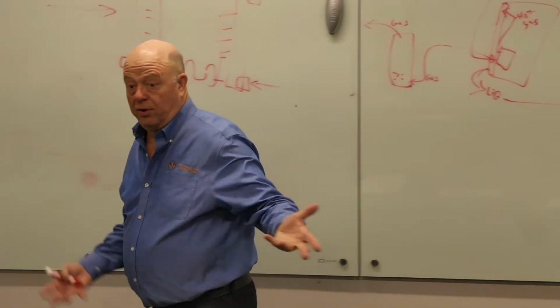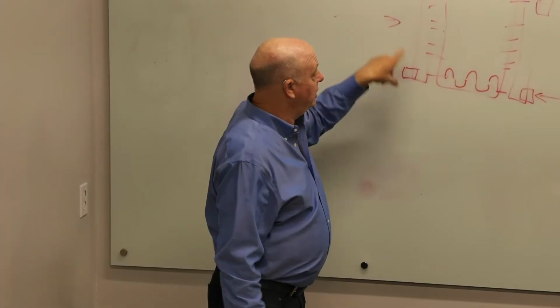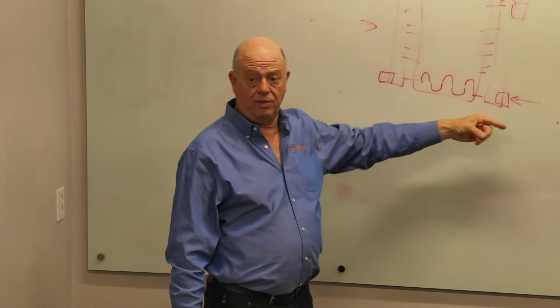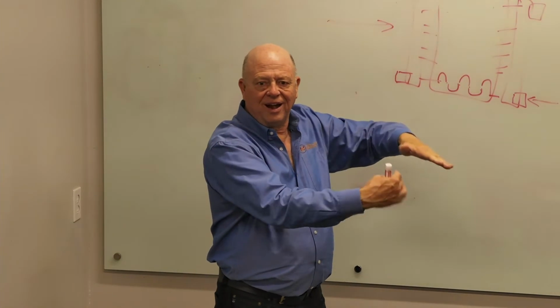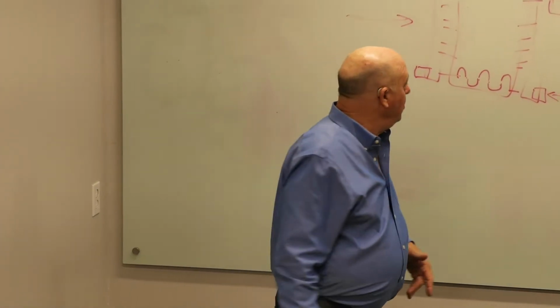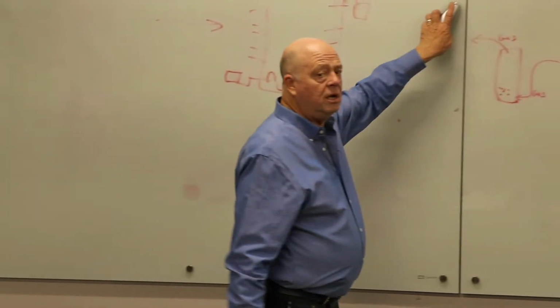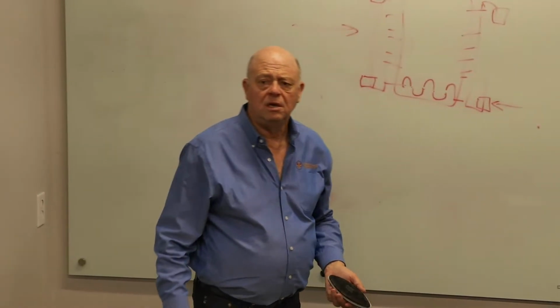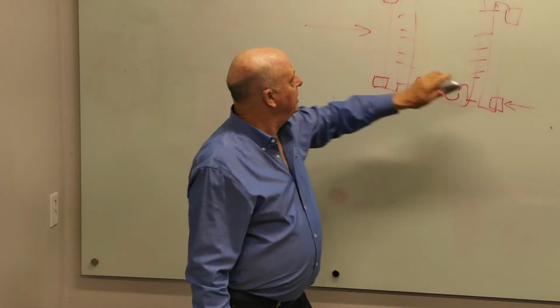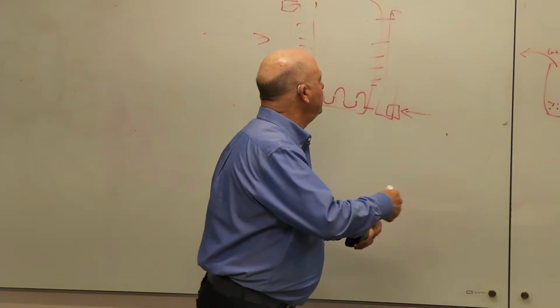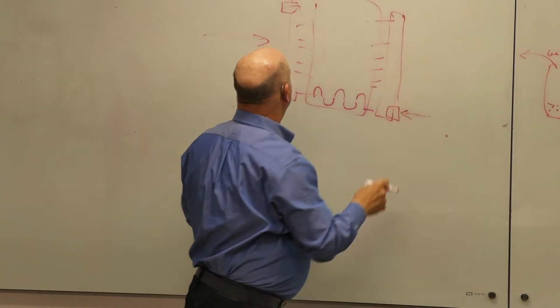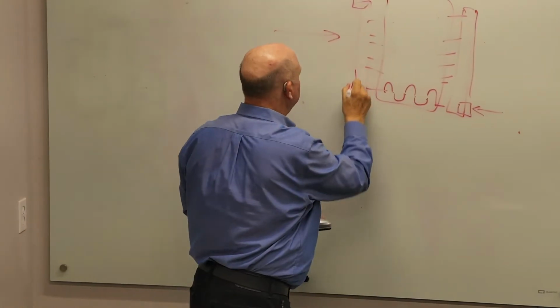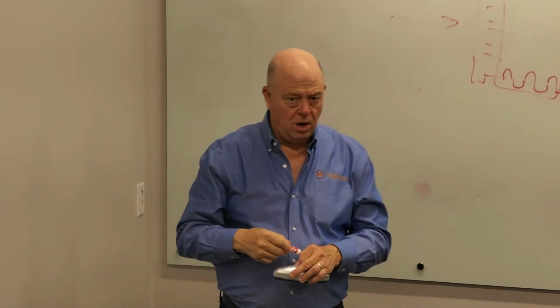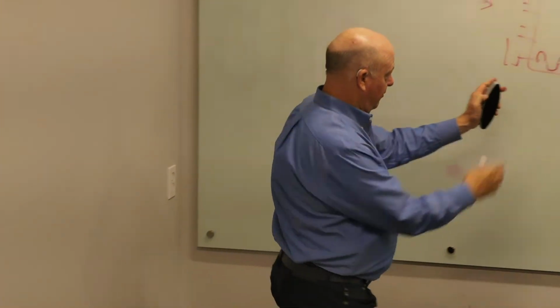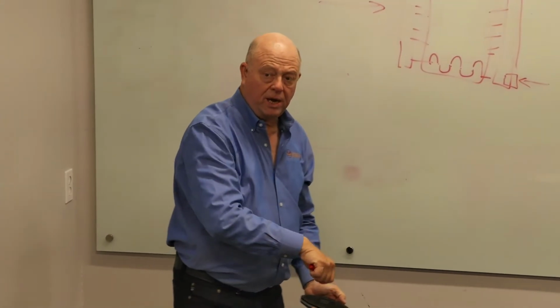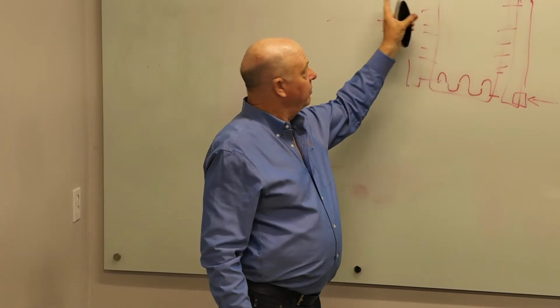Now, in theory, would it matter? If I have 4 connections, I could come in the bottom as long as I came in on the leading side, right? I could do that. But then what happened about 20 years ago is the manufacturers figured out that that's more expensive than it needs to be. And so they started sending them out with only 2 connections. Well, if this is the side where I'm coming in with the pipes, I can come in the bottom and out the top and I'll be fine.